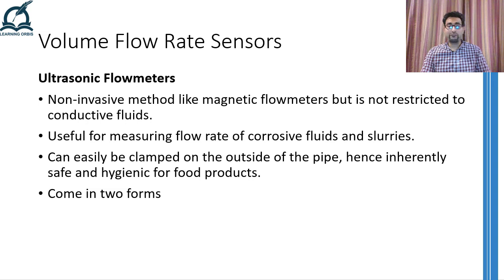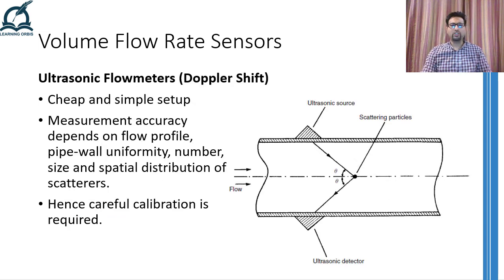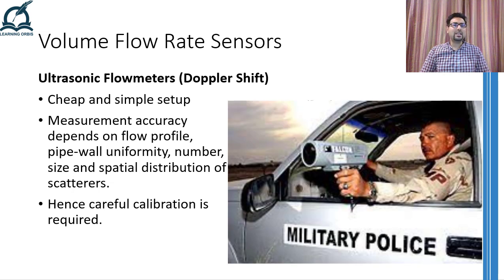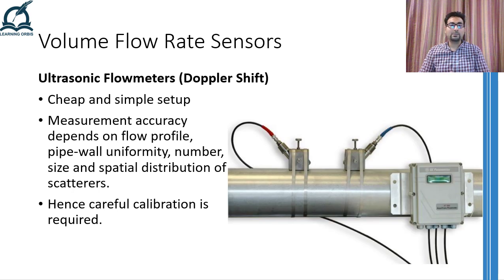Ultrasonic flow meters come in two different forms. One is called the Doppler shift ultrasonic flow meter, whereas the other is called the transit time ultrasonic flow meter. In the Doppler shift ultrasonic flow meter, ultrasonic waves are transmitted by the transmitter and reflected by air bubbles or other particles present in the flowing fluid. The reflections are detected by the ultrasonic detector. Since the reflection was created from a moving particle, the reflected wave will experience a Doppler shift in its frequency. Just like a speed sensor used by traffic police, the Doppler shift in frequency is directly proportional to the speed of the moving particle and hence the speed of the fluid in the pipe.